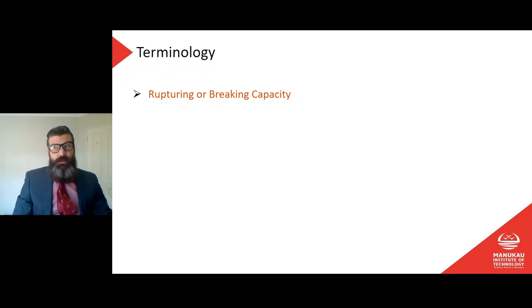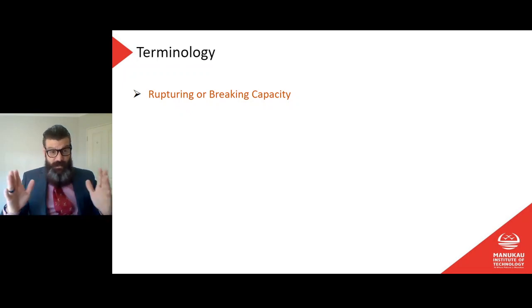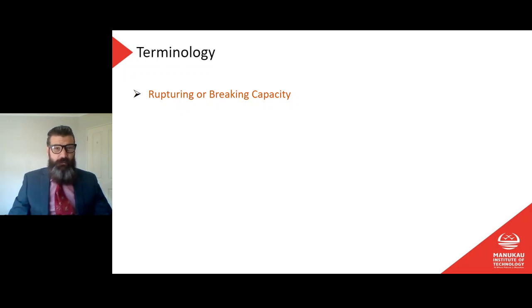What could our alternatives have been? Maybe a higher breaker, a much bigger breaker at the top and a smaller one at the bottom to increase that distance, to give us a bit more discrimination. Maybe not putting circuit breakers at the top at all, although I have a feeling that when you're running off a bus bar system like that, it's actually legally required. I don't know. It was a hassle. It was a real hassle. Something to be aware of, and that's an issue that comes down directly and squarely into this idea of discrimination. Cool. All right, move on.